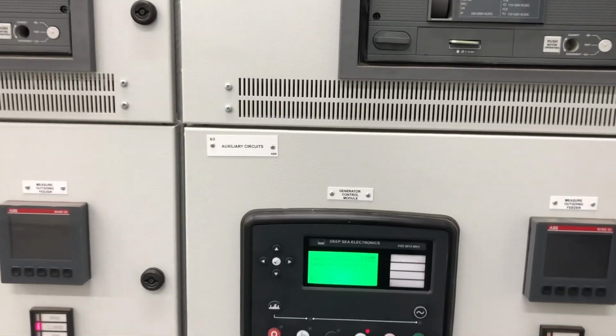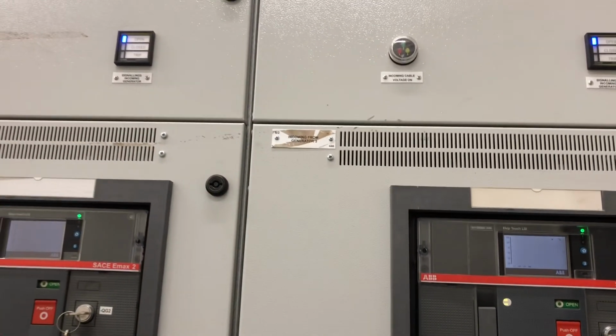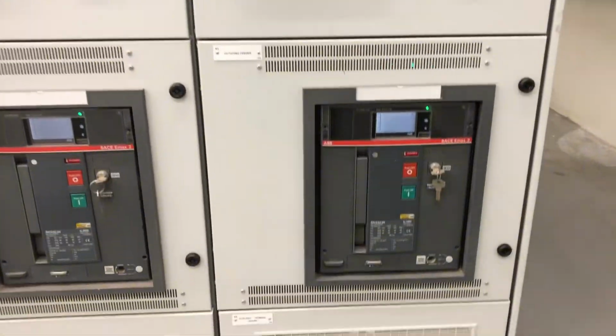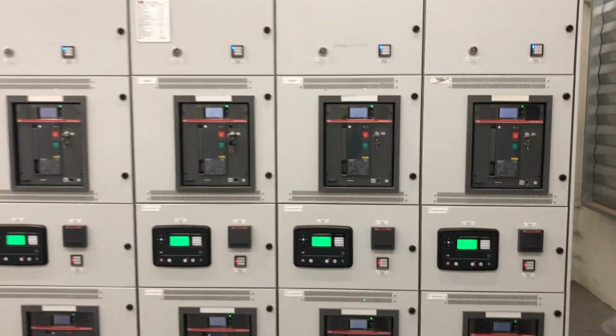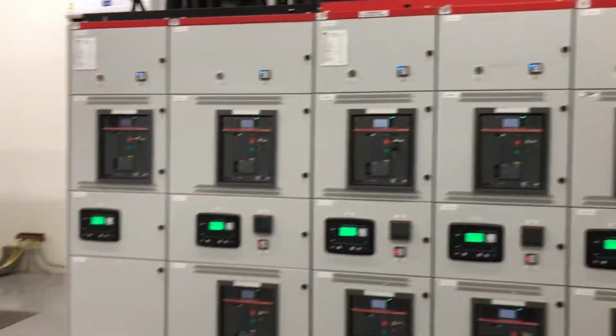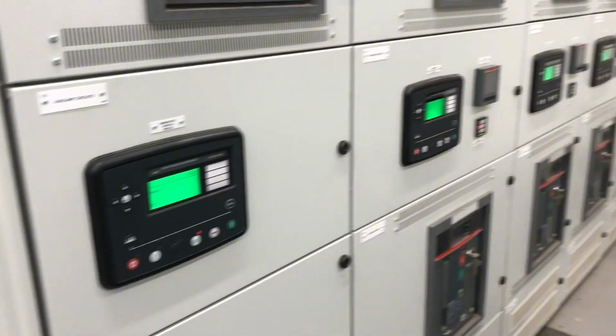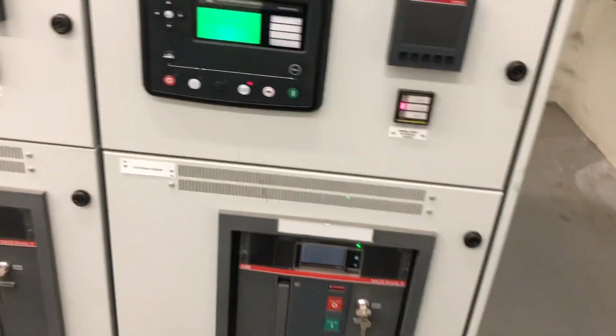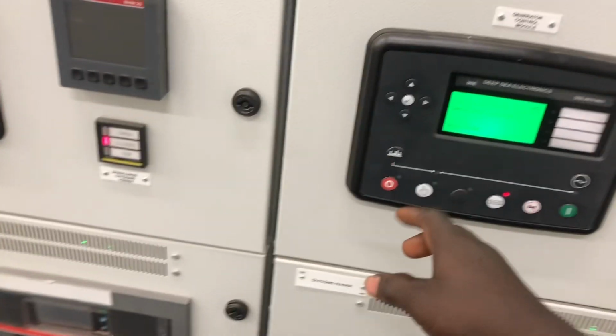So here is the totalizing panel I was talking about. You see, I've already shown you the cables that are coming from the genset. All 5 of the gensets come to this particular place, which is the totalizing. This machine has been scheduled to handle power outage, and these machines are basically set at auto mode. So when we have a power outage, the panels you are seeing here do the switching by themselves from the main grid to the genset.